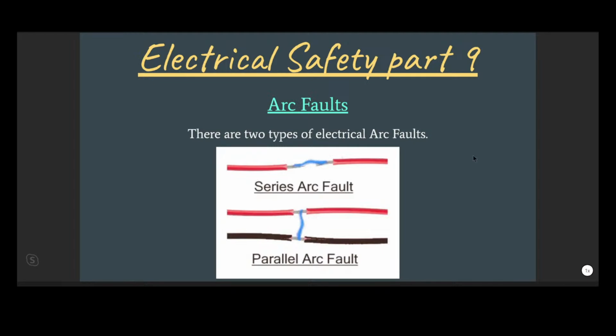We have different types of arc faults - two different types. A series arc fault is like on a light switch, as an example. If you've never done this before, go over to a light switch, put your ear really close to it, and slowly move the switch into the on or off position. What you'll hear is a little pop, and that's considered a series arc fault. It's not necessarily a fault, but arc faults can be just as dangerous to humans and buildings. Either way, that's an intended arc fault - we have to have it. It's an intended arc.